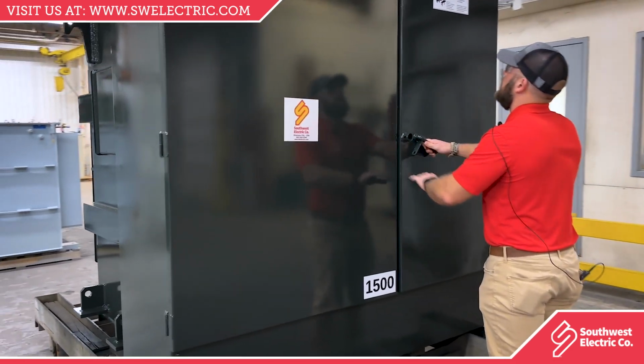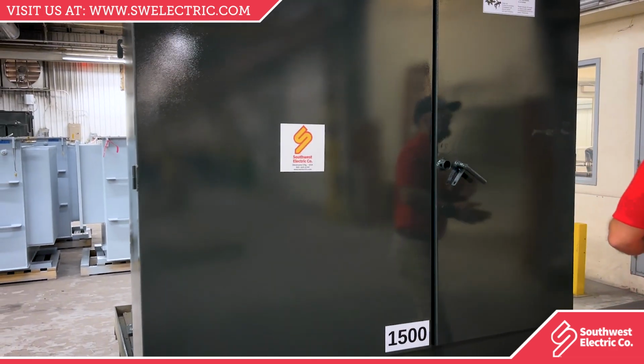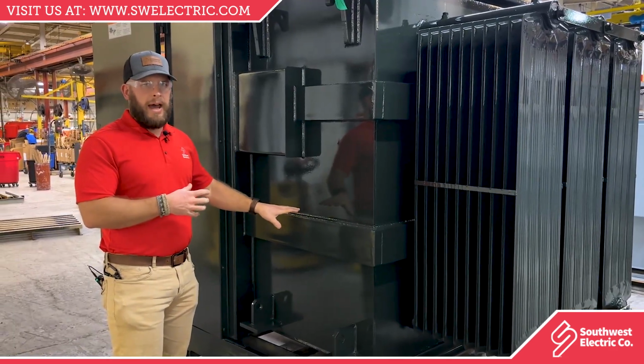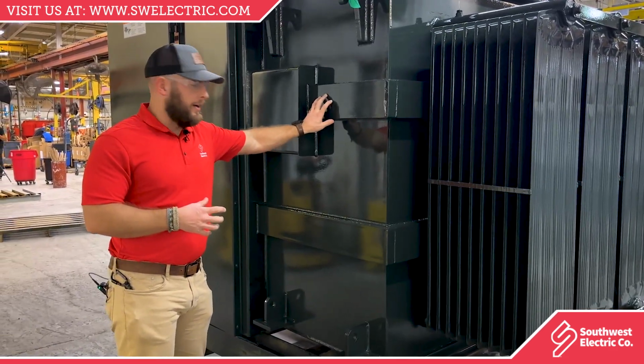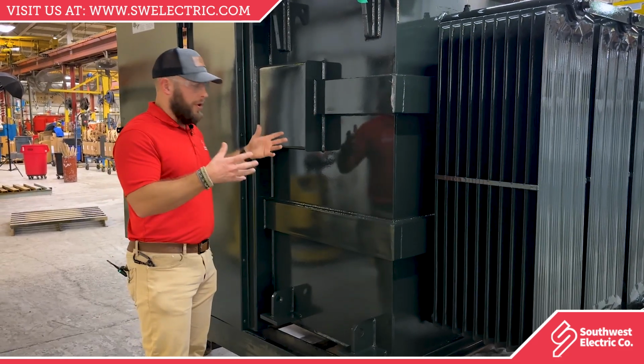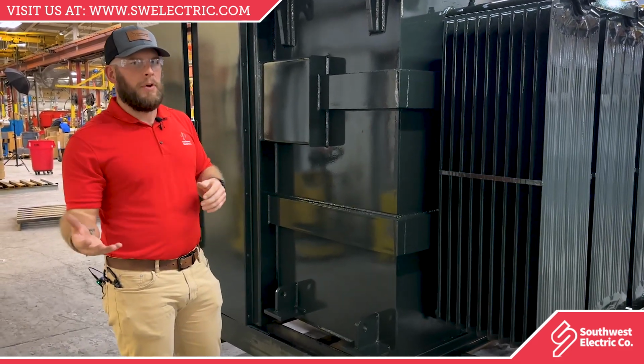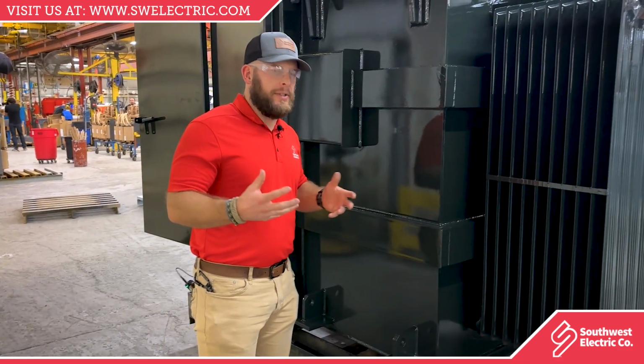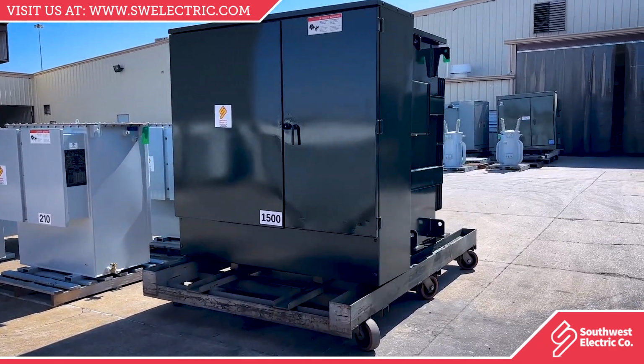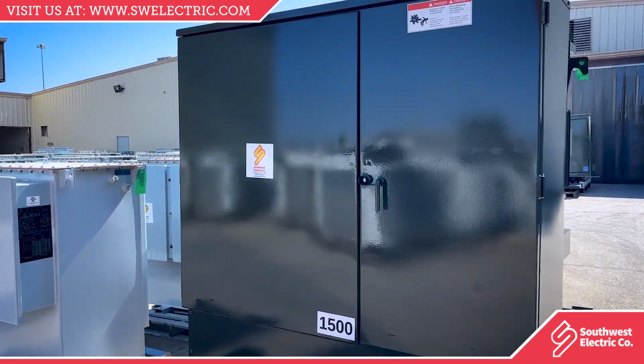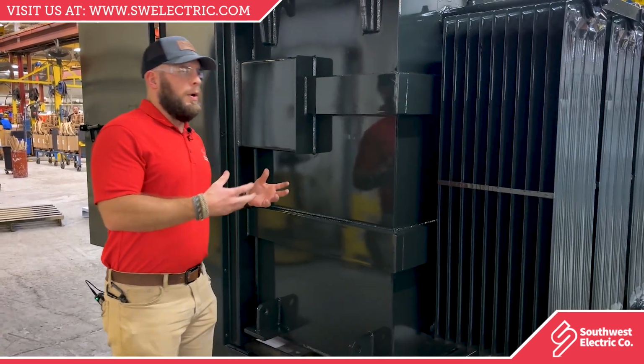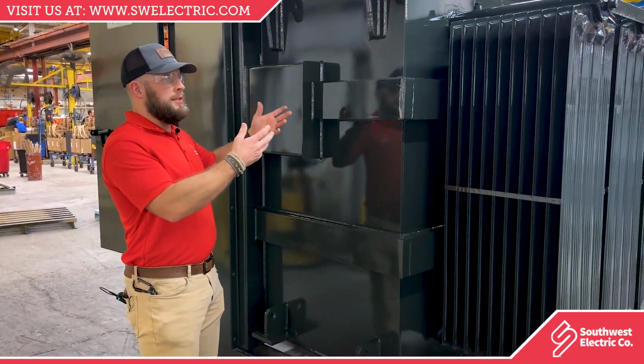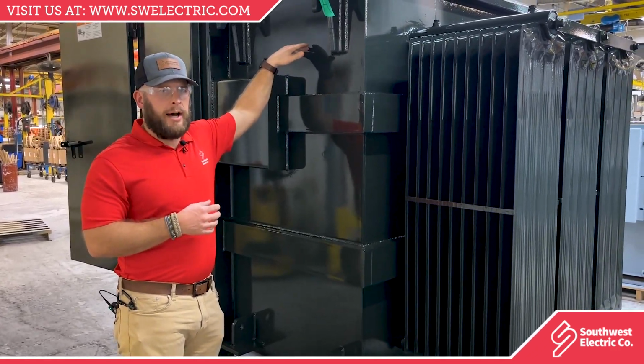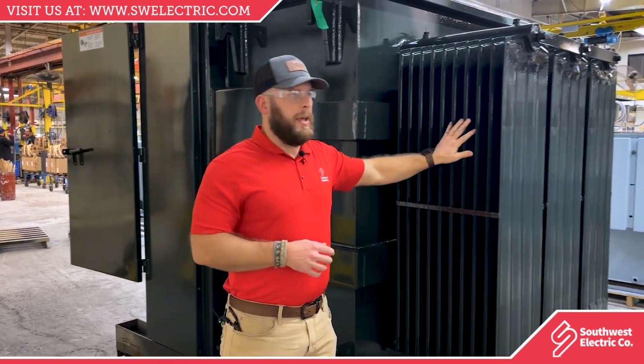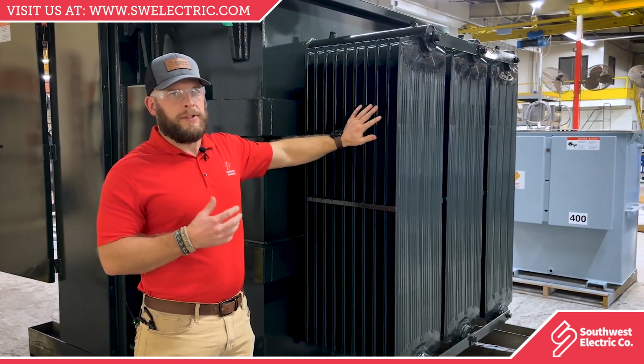The core components of the transformer, all the circuitry is down in the bottom half of the transformer tank. So this is the enclosure that holds all the main components and also holds the oil. So as the main components inside the transformer tank start to heat up, it will start to heat up the oil around it. And as that oil heats up, it will start to rise and come up to the top or near the top of the transformer. That's where these come in. This is what essentially dissipates all the heat.